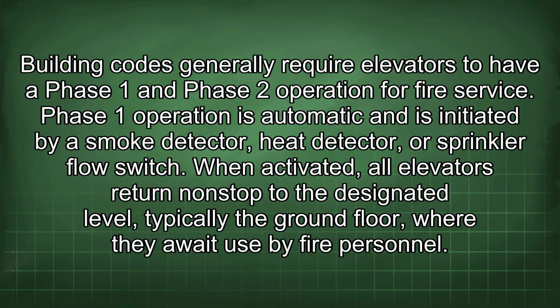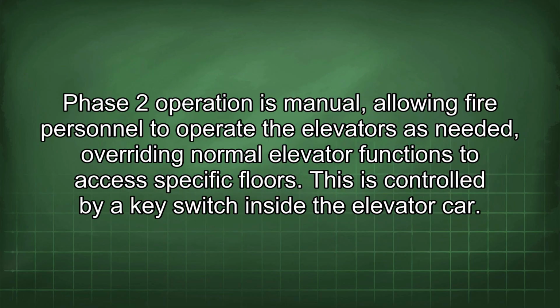Building codes generally require elevators to have a Phase 1 and Phase 2 operation for fire service. Phase 1 operation is automatic and is initiated by a smoke detector, heat detector, or sprinkler flow switch. When activated, all elevators return non-stop to the designated level, typically the ground floor, where they await use by fire personnel. Phase 2 operation is manual, allowing fire personnel to operate the elevators as needed, overriding normal elevator functions to access specific floors. This is controlled by a key switch inside the elevator car.